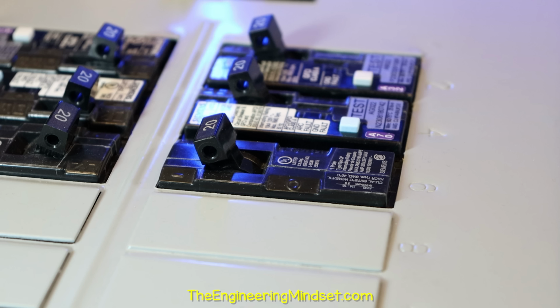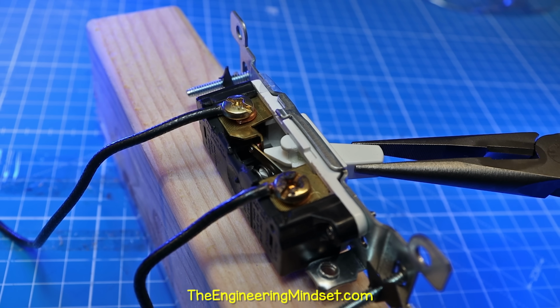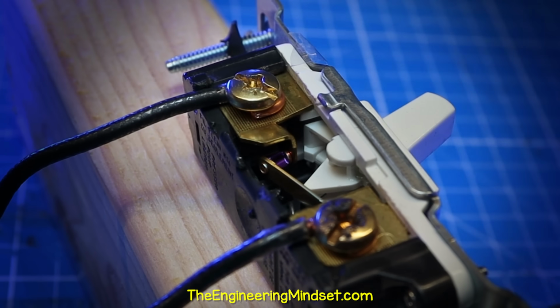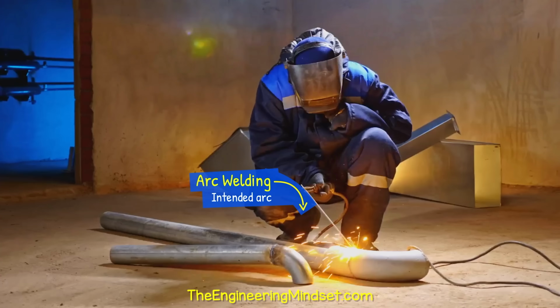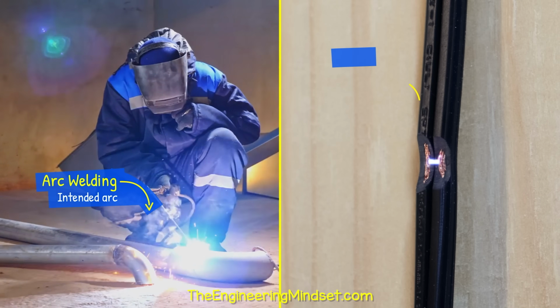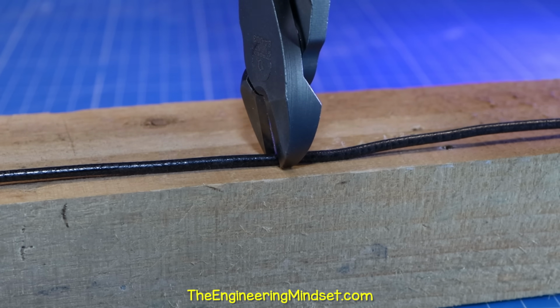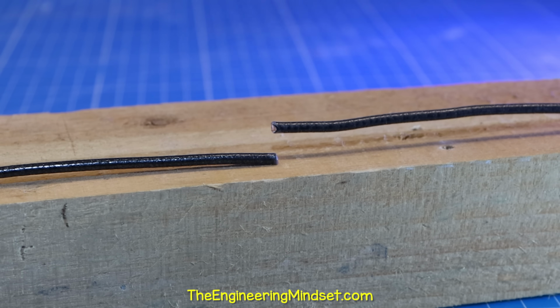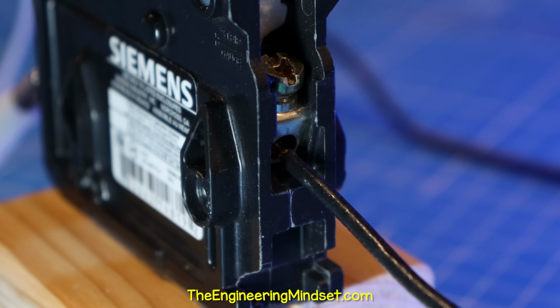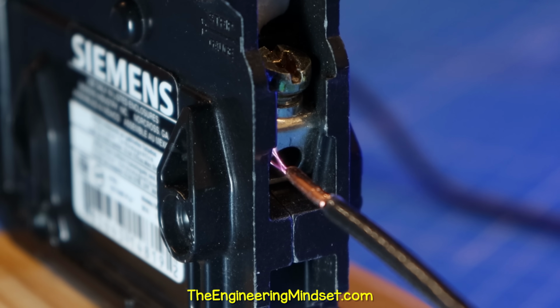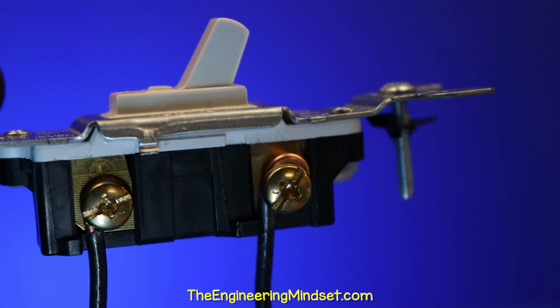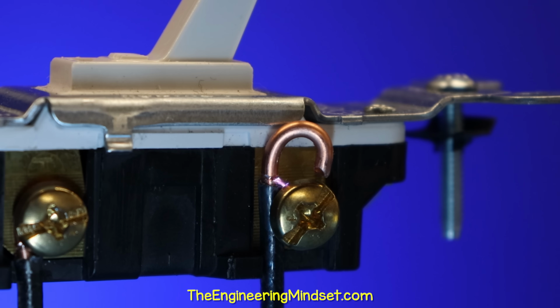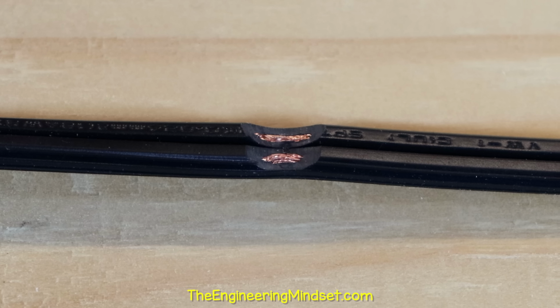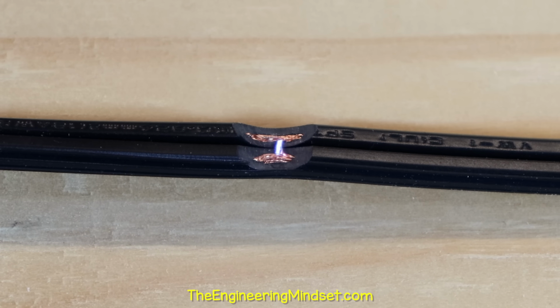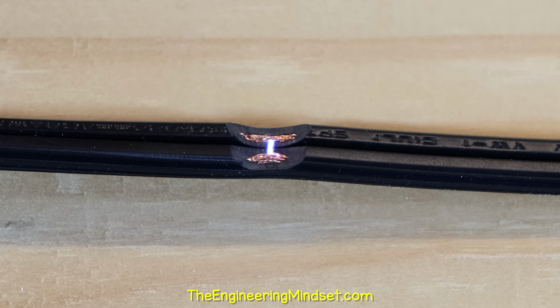When a switch flips or a breaker trips, an arc can briefly form between the contacts as they open. But this isn't really a fault. An arc fault is unintended. For example, if a wire is cut or broken, an arc can form between the conductor. If the wire is pulled from the terminal, it can also arc. If the terminal on a switch or outlet is loose, it can also create an arc. If the insulation on a wire is damaged, an arc can form between the conductors.